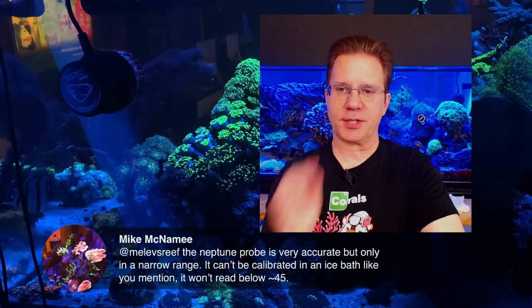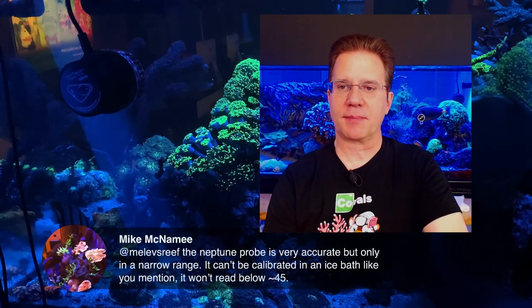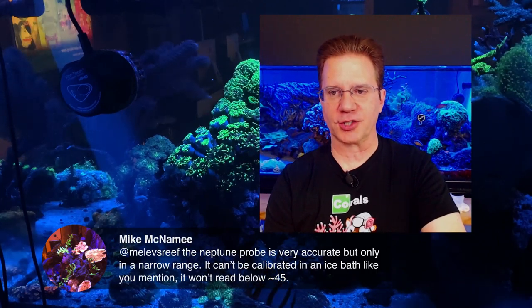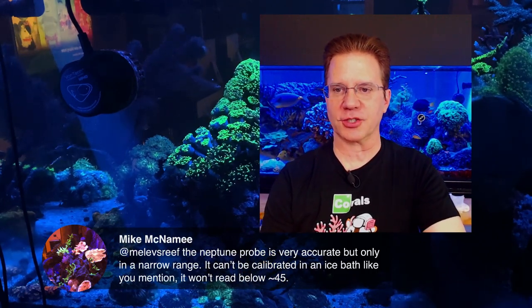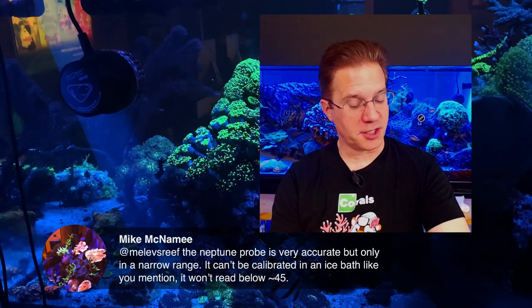Mike chimed in about the temperature probe. He says the Neptune probe is very accurate, but only in a narrow range. It cannot be calibrated in an ice bath like you mentioned. It can't read below 45 degrees. Good to know, thank you, appreciate that.